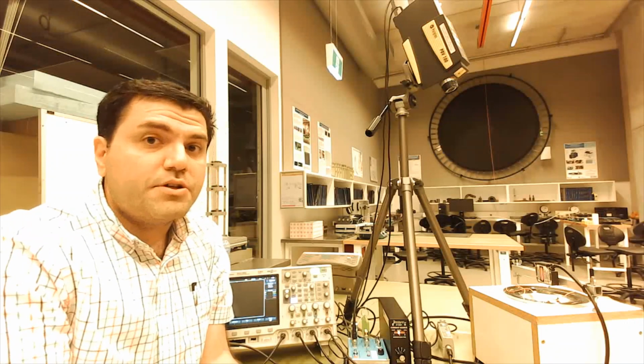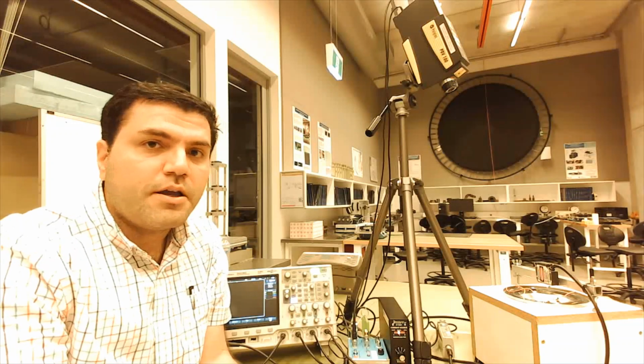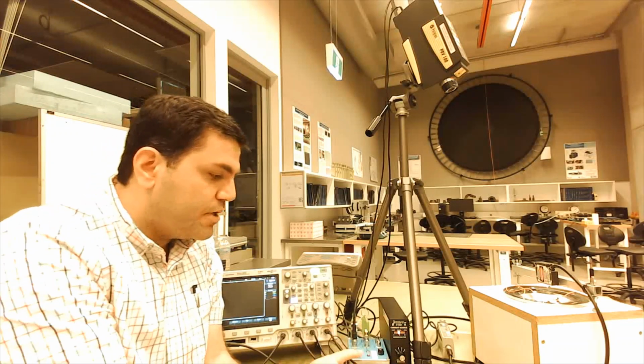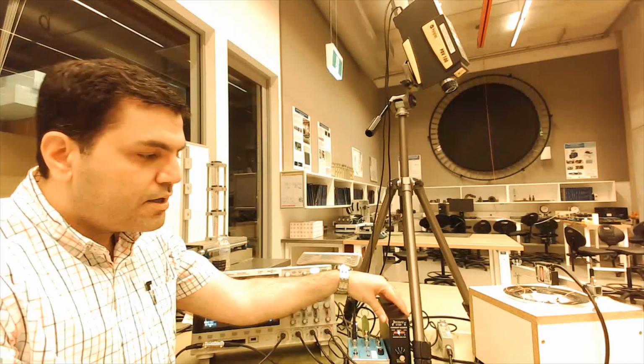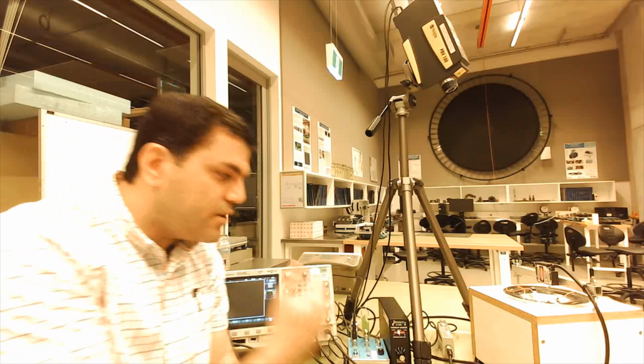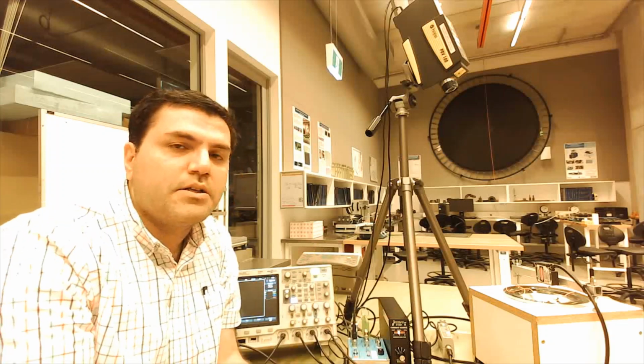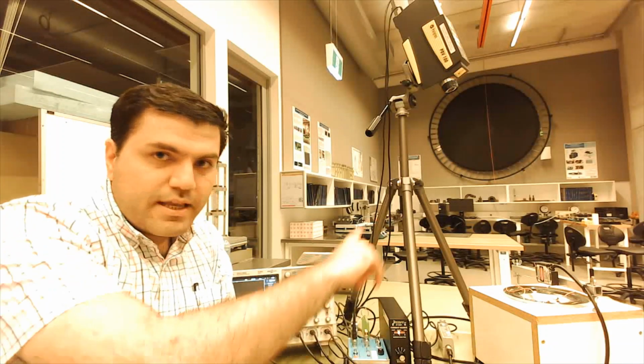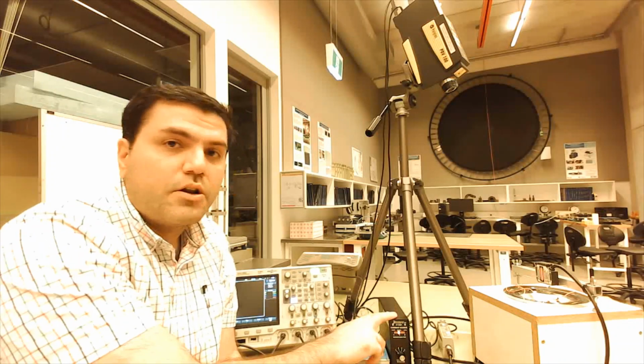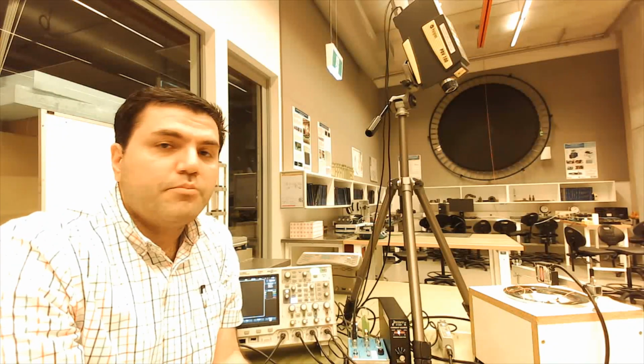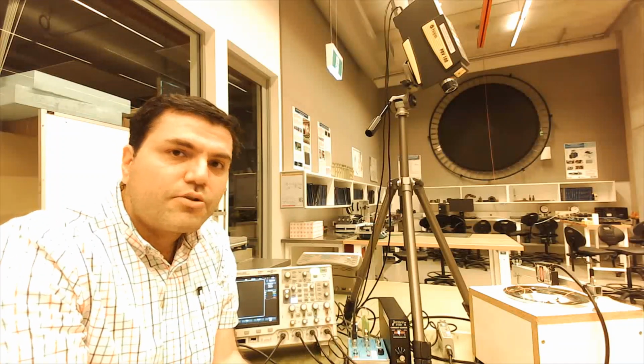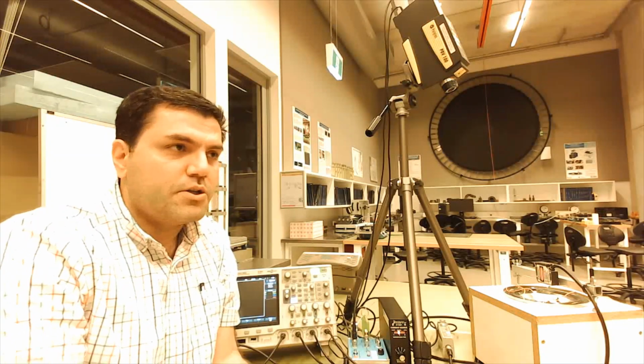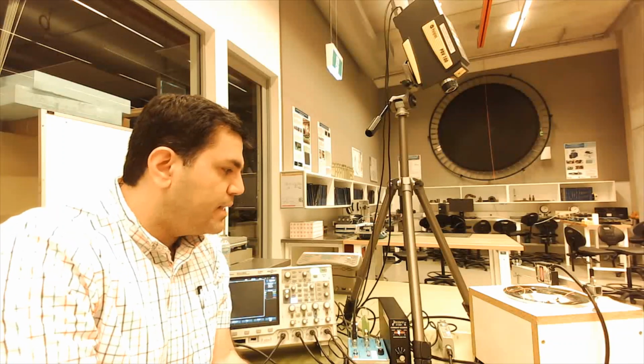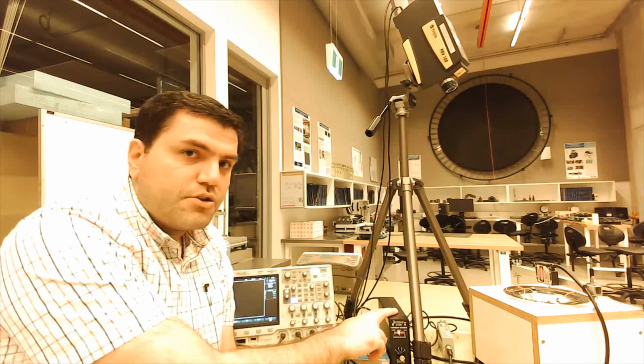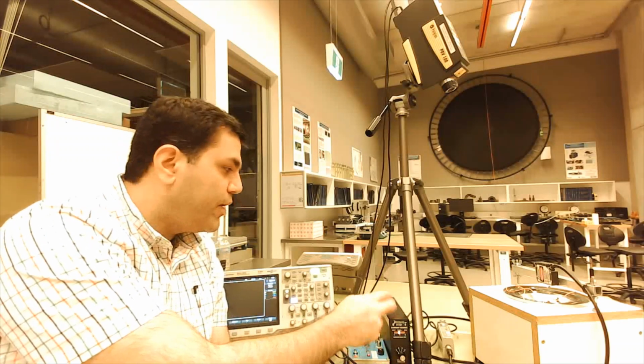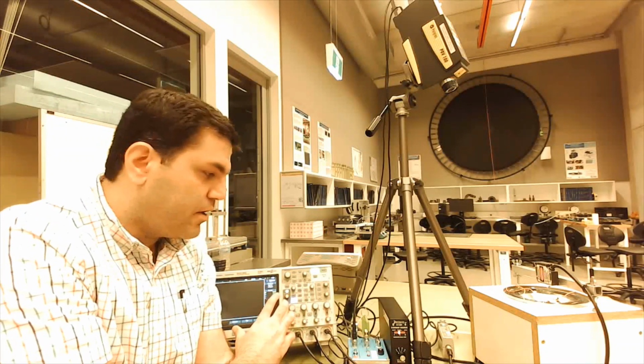These IEPE accelerometers also need a constant current supply, which here we provide with this signal conditioner. The signal conditioner provides the current supply, and the output of the accelerometer also goes into the signal conditioner. Because the signal conditioner also does filtering, we can filter noise and also increase the signal to noise ratio. The output of the signal conditioner goes into the oscilloscope to collect the signal.